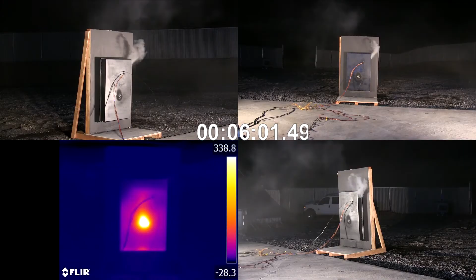Then internal temperature starts to rise, and once you get over 165 degrees Fahrenheit, you can start to get what we call thermal runaway, where the internal temperature of that battery continues to increase. As we know from the Fire Safety Research Institute's research, heat creates pressure, and so you're creating that internal pressure. And here, you start to see it.